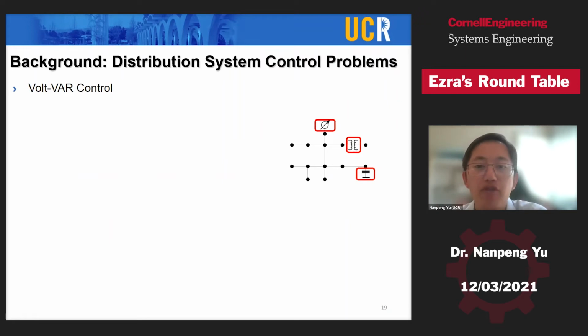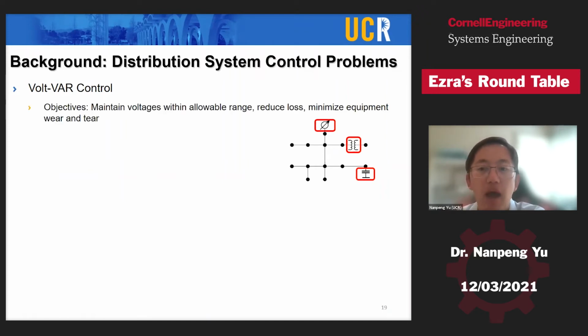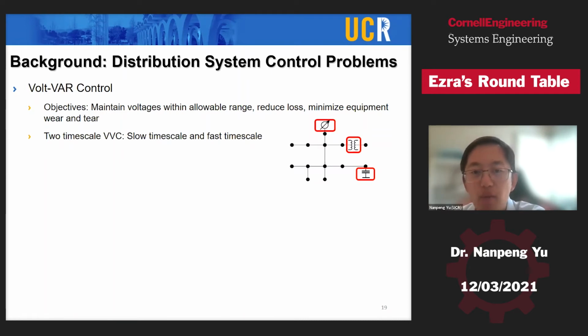So next, I'm going to briefly talk about two distribution system control problems that we tackled. The first one is Volt-VAR control. Basically, we're trying to control the nodal voltages in the system and reduce the network losses. We also want to minimize the equipment wear and tear. So in the distribution system, conventionally, we have voltage regulating devices, which are circled here. We have voltage regulators at the top of the feeders or substation. We have capacitor banks installed throughout the feeders. We also have OLTCs, on-load tap changing transformers, that impact local voltage. And these are what we call slow time scale voltage control. And we also have smart inverters installed for the solar PV systems. These devices could change their reactive power setting in close to real time.